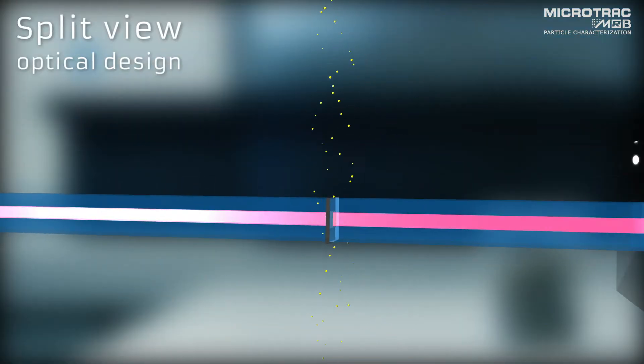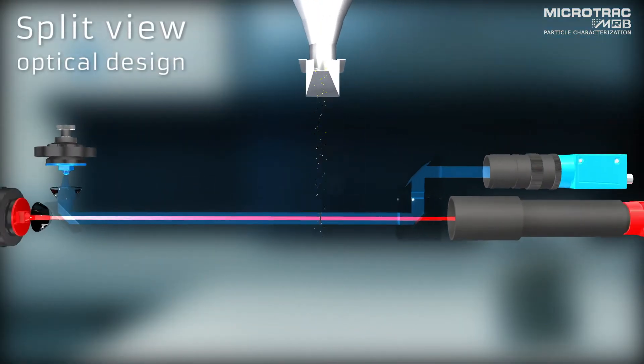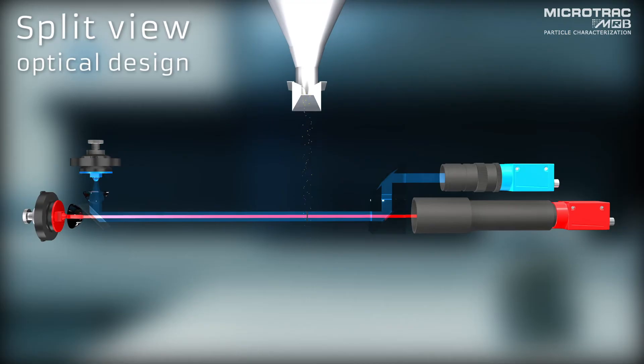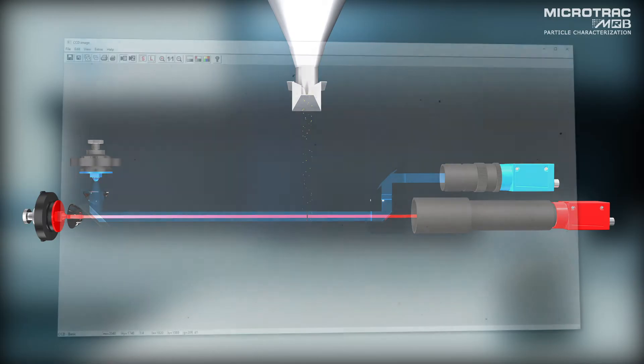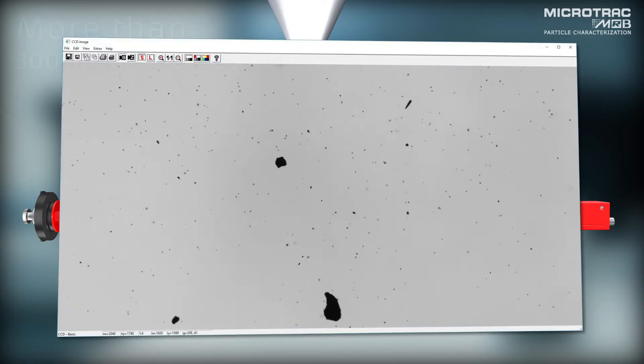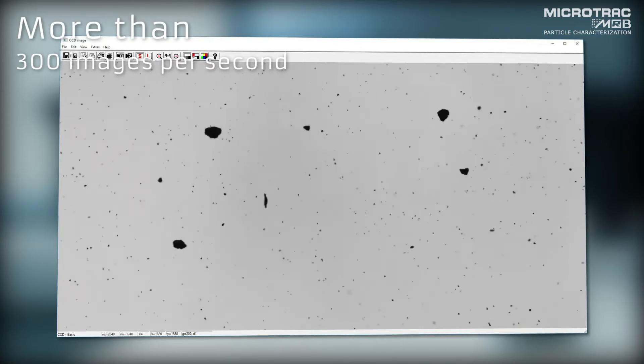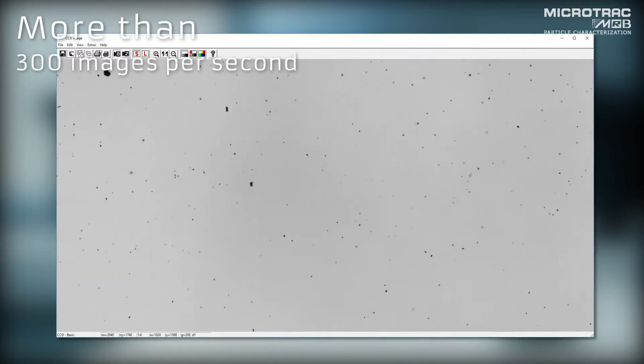The CamSizer X2 features a new innovative split view optical design in which both cameras share the same focal plane. The system records more than 300 images per second, with each image containing several hundred particles.